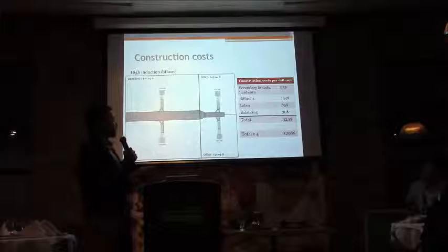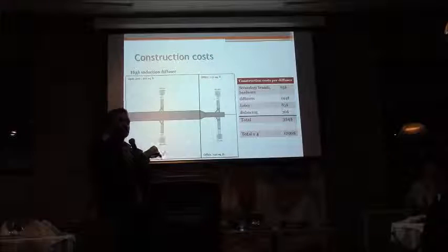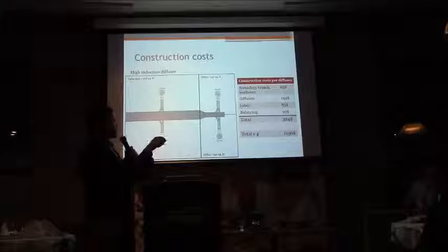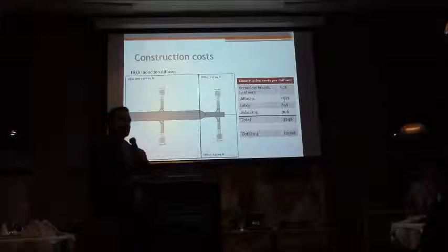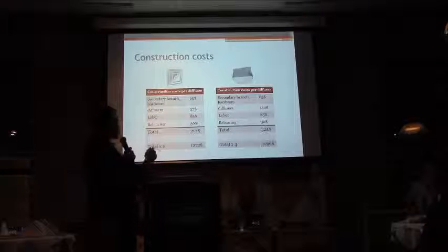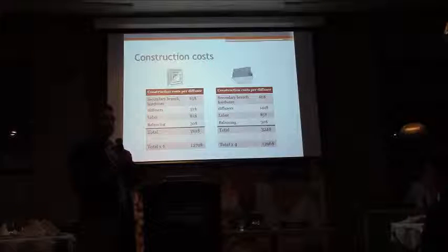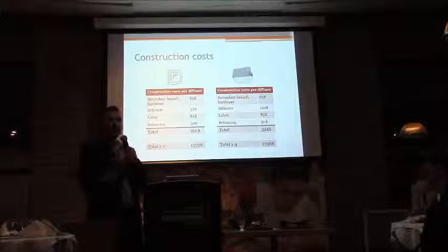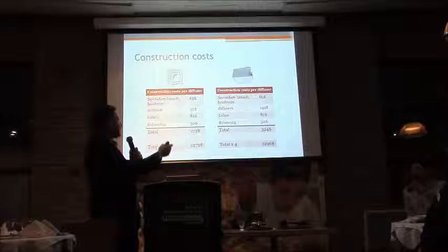The same cost as before, except for the diffuser, which is estimated at $144, including the plenum. So it's a bit more expensive for the diffuser, but it's a total of $324, but instead of multiplying by 6, you're multiplying by 4, because there's less diffusers. So the total is $1,296. And if we compare both of them, it's $1,272 versus $1,296. So it's approximately the same cost for high induction versus a standard cone diffuser at the end of the run, including installation, hardware, balancing cost. But you have the added benefit of more comfort and more energy savings.